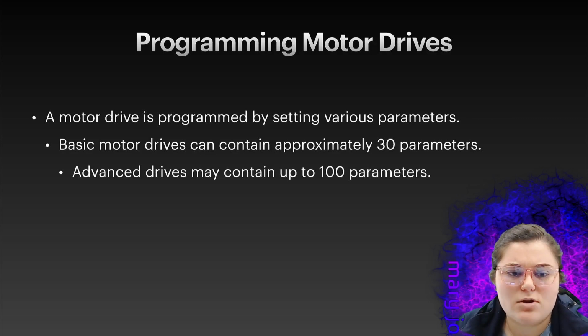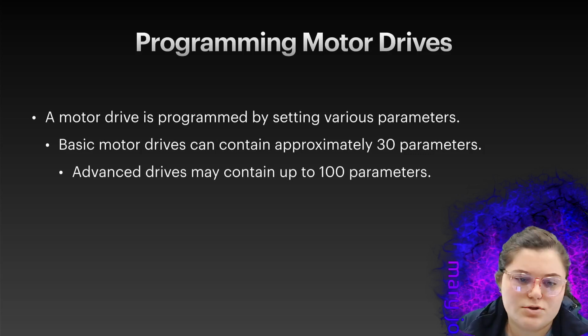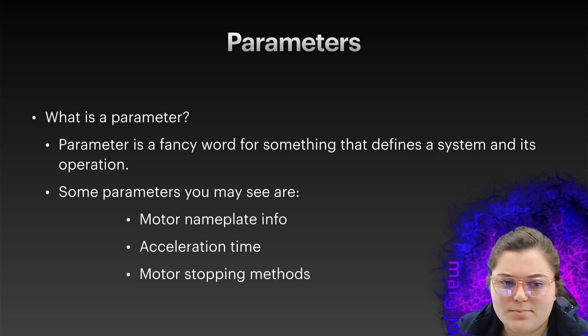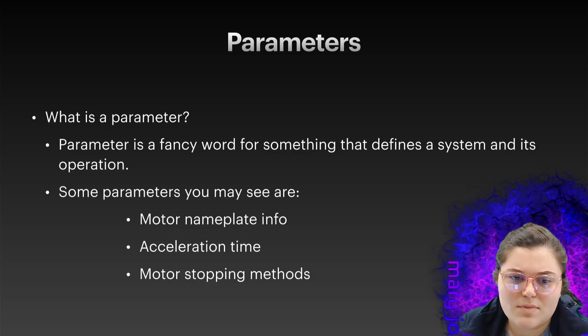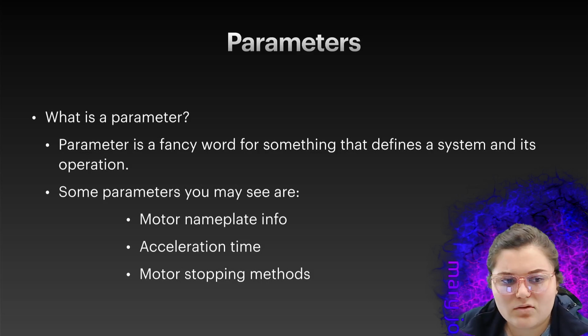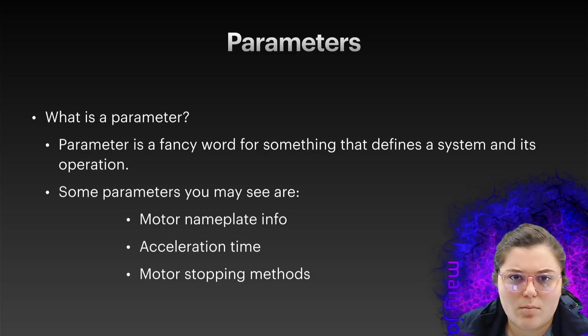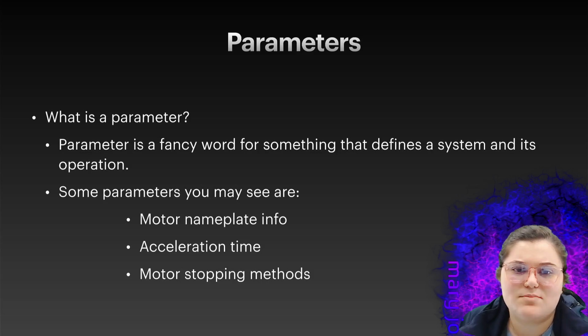Programming motor drives. A motor drive is programmed by setting various parameters. Basic motor drives can contain approximately 30 parameters, where the advanced drives might contain up to 100 parameters. So what is a parameter? You hear that word a lot. Parameter is just a fancy word for something that defines a system and its operation. So a parameter is something that you're going to set to define that motor control system. Some parameters you might see are motor nameplate info, acceleration time, and motor stopping methods. You're going to set these parameters depending on what application you're having to use, whether it be in lab or in a job or whatever you're doing. You're going to have to set these because that motor or that circuit cannot bypass these parameters.